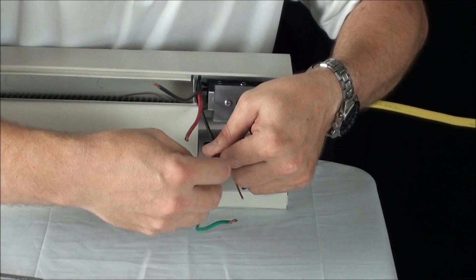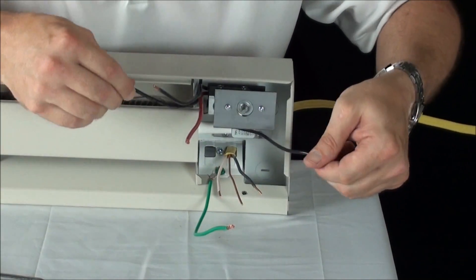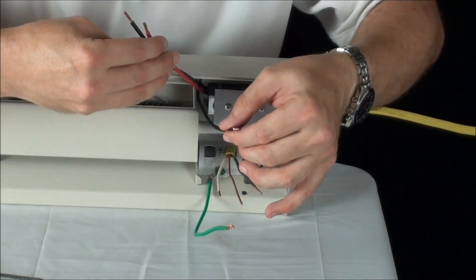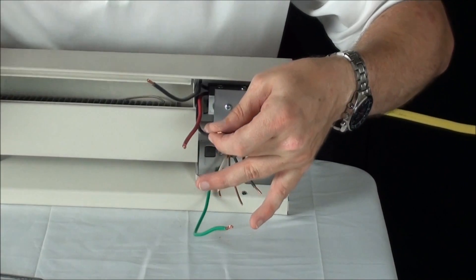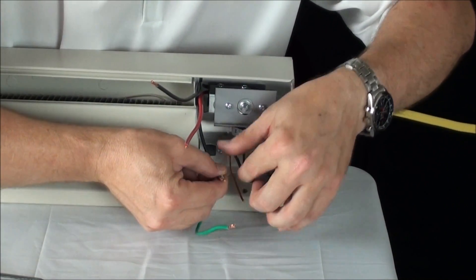Disconnect the two wires that come inside the baseboard. These are your element wires. Hook one of the element wires and one going across the top of the baseboard to the neutral wire from your power source.